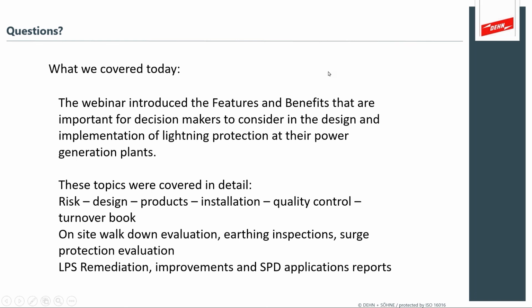If it's a highly critical area, like a motor control room or a concentration of electronics in some shed, we go for methods where we can keep lightning current separate, like you mentioned, Mark, an isolated lightning protection system with HVI, or a system that just maintains the calculated separation distance.